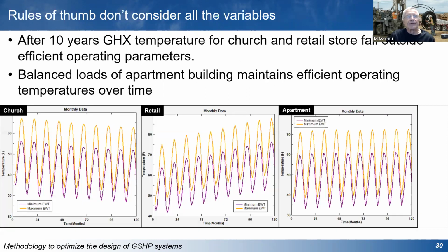So if we're looking at the long-term operation of a system like this, they're going to operate differently, even though the buildings have exactly the same peak heating and cooling loads and are built across the street from each other. The church, because we're extracting more heat from the ground than we're putting back in, is going to start getting too cold after about 5 or 10 years. The retail store, on the other hand, is going to start getting above the temperature that we want to see them operate at. If the loads are fairly balanced, then we're going to see a system that is stable and going to be operating continuously for the life of the building.